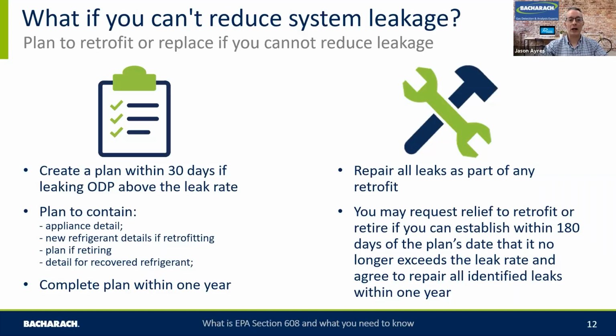What else can you do? And it really falls into 2 areas. Either retire the piece of equipment, i.e. remove it and take it out of service, or retrofit the refrigerant in that system. The plan has to contain some key details: the appliance details, what the new gas is going to be, the records of removing that gas, and the plan if retiring it, when, and what that equipment is going to be replaced by. Once you've got that plan, you've got a year to enact it. So as long as you complete the replacement of that equipment or the retrofit of the gas, if you're going to do that instead, you've got a year to do that.